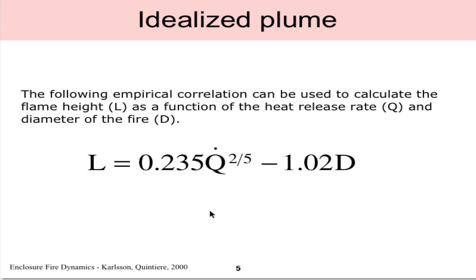This equation from the textbook shows L, the physical flame height, as a function of Q, the total heat release rate, and D, the diameter of the fire. Notice the units on this: Q is in kilowatts and D is the diameter of the fire in meters or the equivalent diameter in meters.